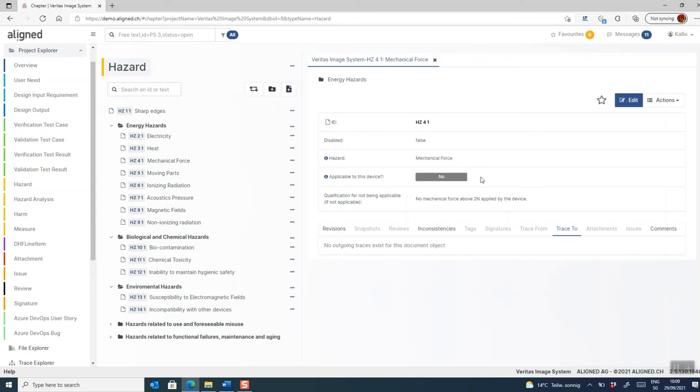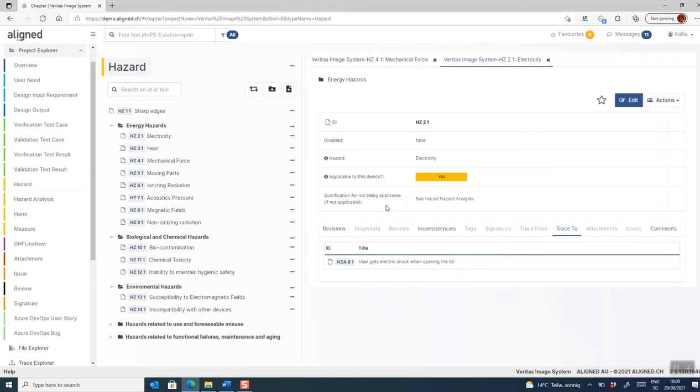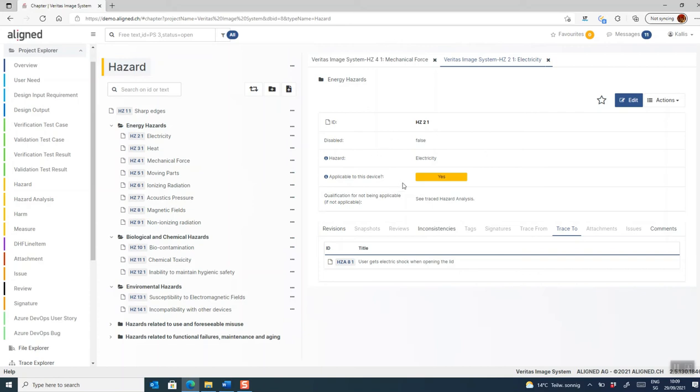If it's not applicable, you're supposed to state why that is the case, meaning that you qualify the answer, why it's not applicable. And if it is applicable, you select yes. And now we will create a trace to a hazard analysis item where we write down the identified hazard and perform an evaluation. The idea is that you go through all these generic hazards and evaluate them, whether they are applicable to your device or not. And in the cases where they are applicable, you can then create hazard analysis items.